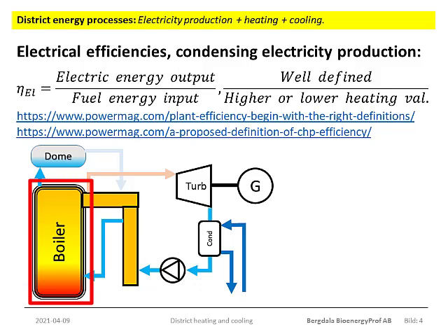We have a boiler, the walls of which contain enclosed water at a high pressure, say 150 bar. Inside the boiler volume is the fire, and that could be burners or grate firing or gas firing or oil or whatever. So heat from the fire is transferred to the walls and heats the water to the boiling point, and then the water enters into the steam dome, which is usually above the boiler. In the steam dome is an equilibrium of steam and liquid water.